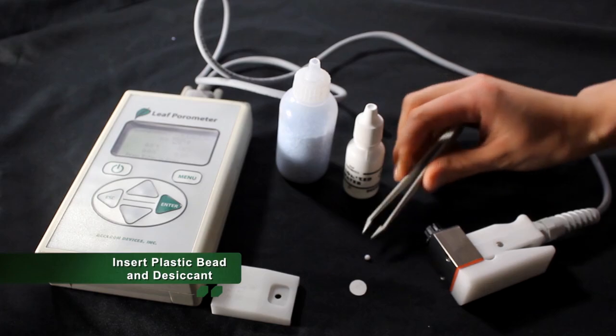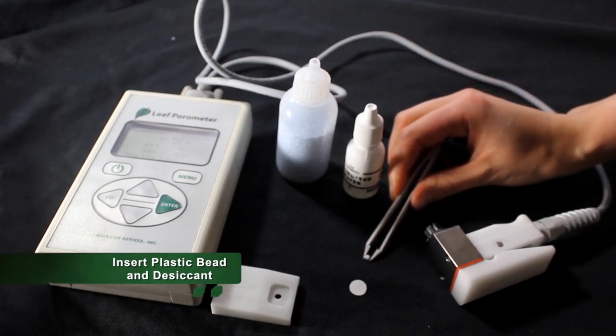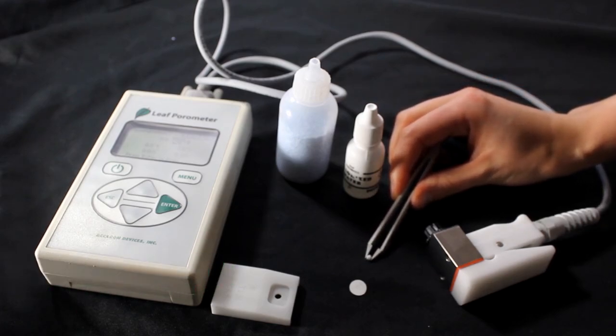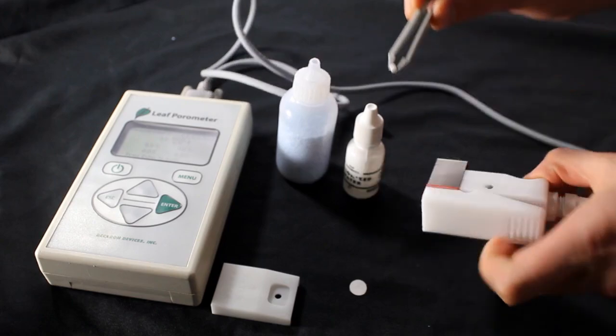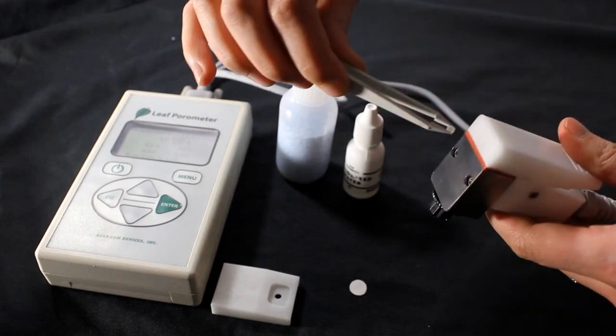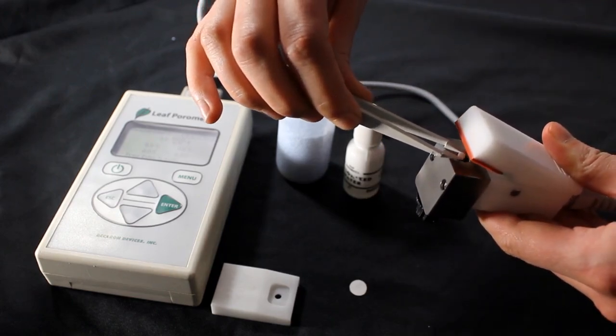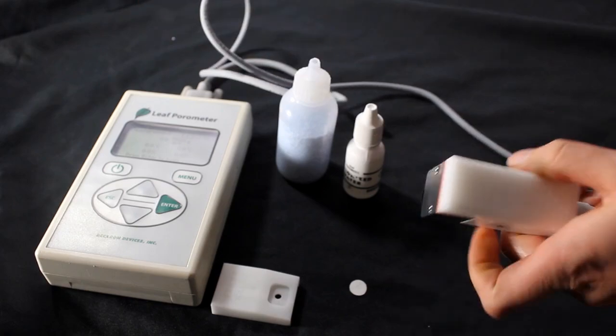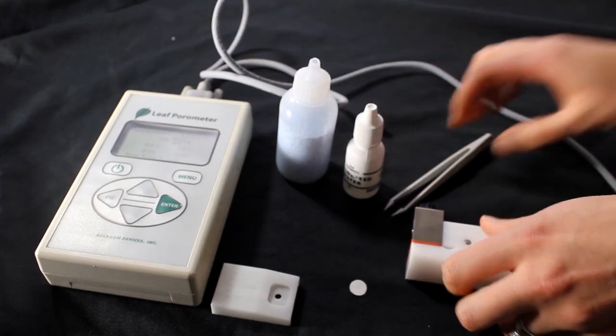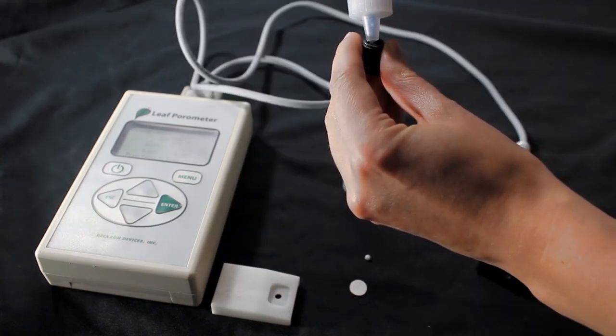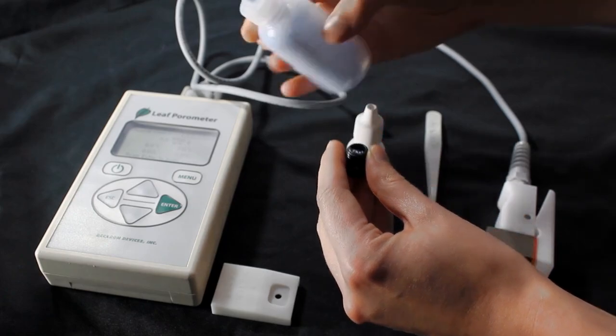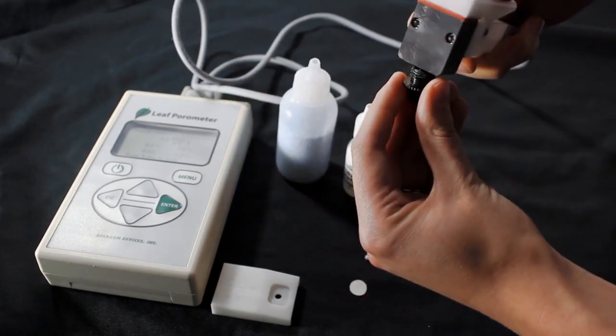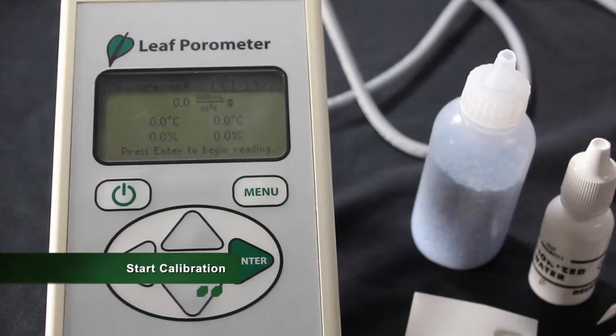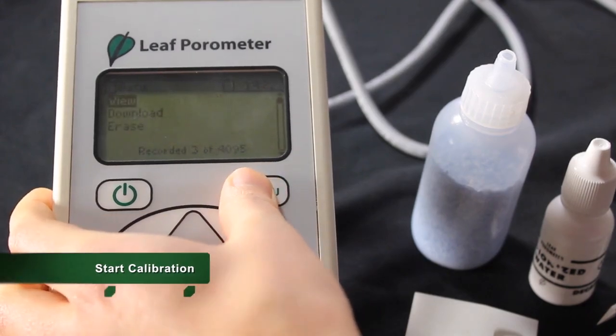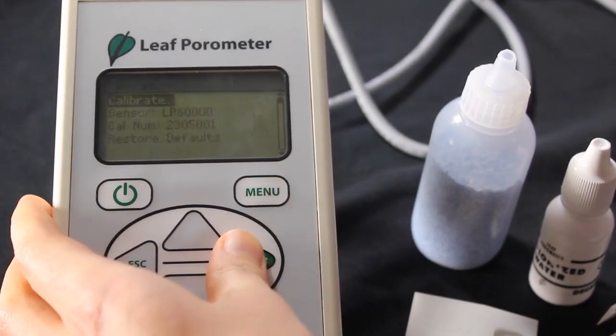Before you begin the calibration, place one of the plastic beads included with your kit into the aperture of the sensor head, like so. The bead will help mix the air in the chamber, expediting the equilibration process. Once the bead is inserted, close the sensor head clip. Keep the clip closed to prevent the bead from falling out. Check to make sure that desiccant has been loaded into the screw cap and that the cap is securely attached to the sensor head. To start calibration, select the Calibrate option on the Configuration Calibration submenu.